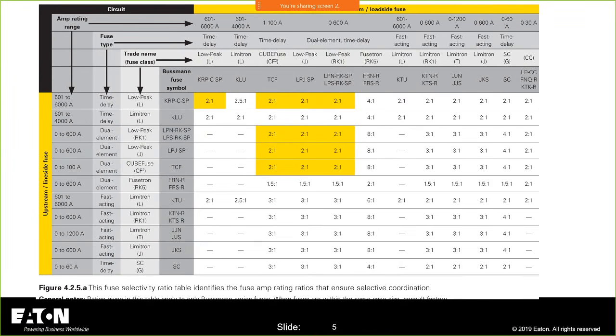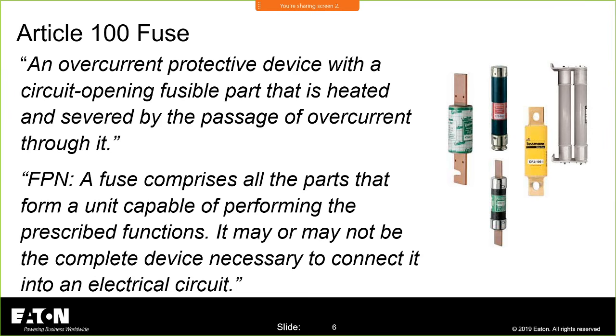And now we are going to go to our regularly scheduled program, and we're going to start talking about the fuse. Okay. So the fuse. The fuse is defined in Article 100. And basically it's going to open. It's going to sever the circuit in some form or fashion by heating an element that's inside. It is not reusable once you've spent that fuse. We do not say blown fuses. We say opened fuses. And I know our fuse guys are sensitive in that regard. So I know we probably have a few of them on the phone, so we'll treat them well.